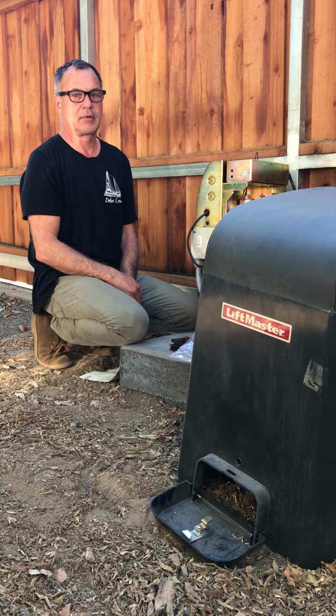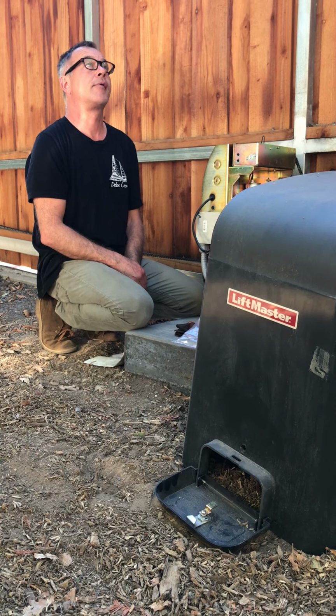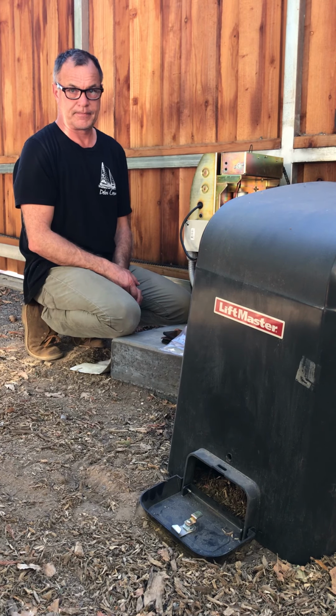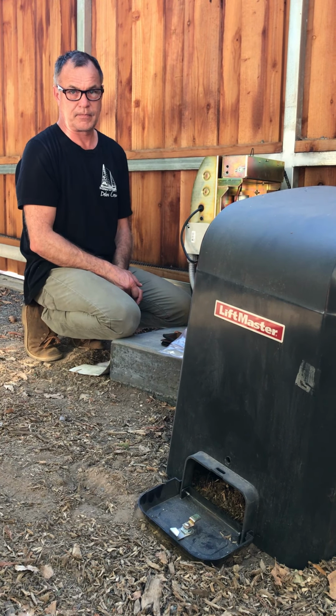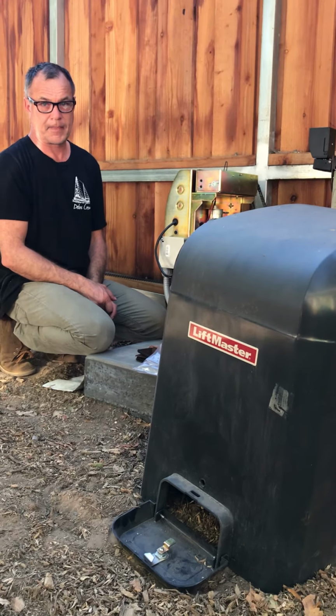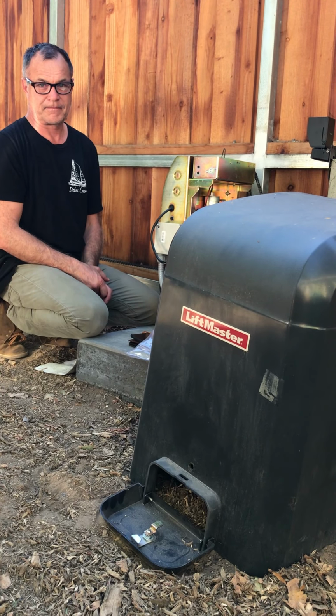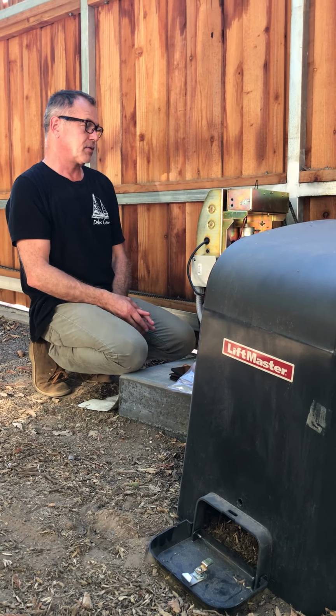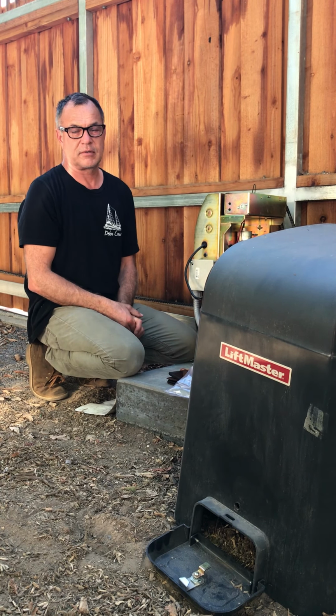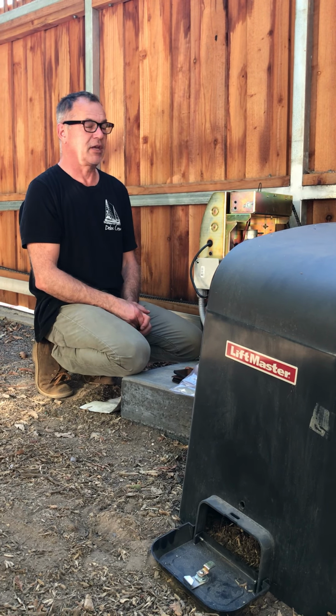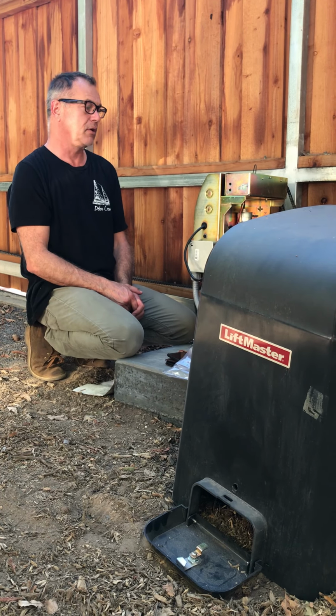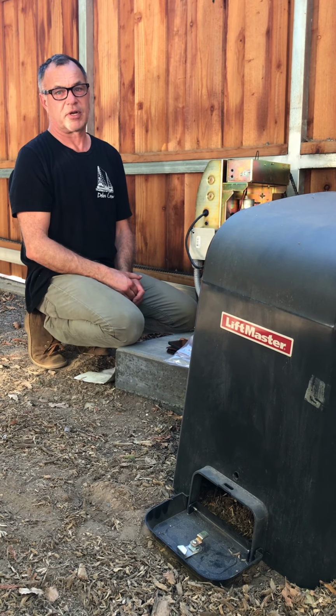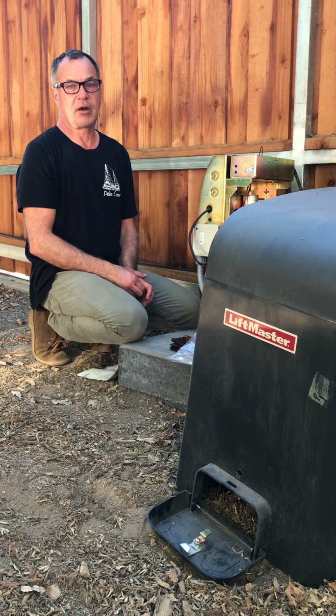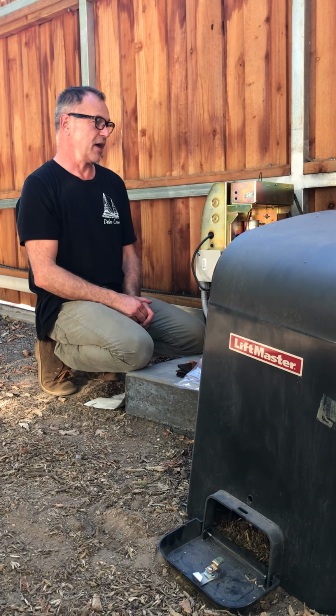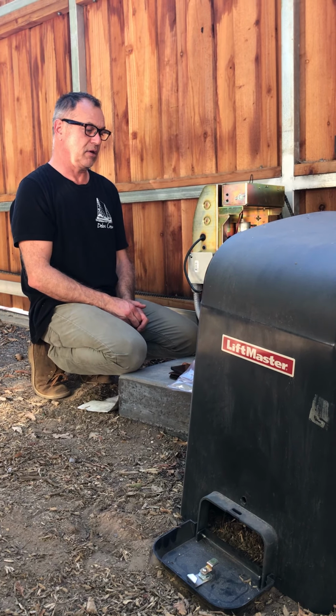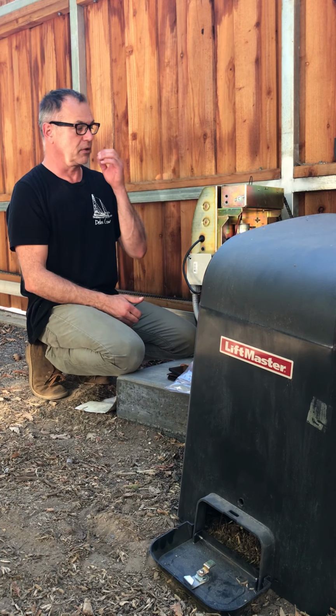Hi, I'm here with Pete and we are troubleshooting the LiftMaster, and Pete will tell us about what troubleshooting techniques he's gone through in the past couple of months. Go ahead, Pete. So pretty much we've got a LiftMaster SL3000 slide gate operator, new installation, and we're trying to troubleshoot a couple different error codes, and primarily we're getting an error code 9.5, which means that the unit thinks that the motor is overloaded.